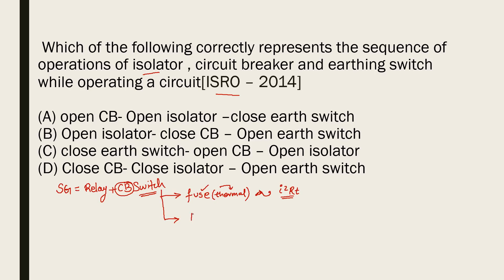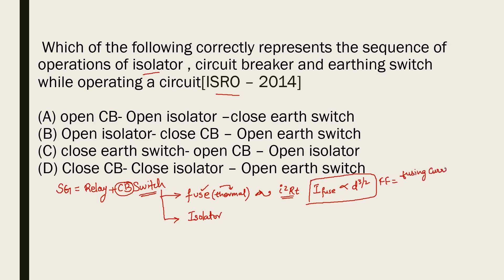Another type of switch is the isolator. The fusing current — the current at which the fuse blows off — is directly proportional to the physical dimension, i.e., diameter to the power of 3/2. There is also a quantity called the fusing factor, where fusing factor = fusing current ÷ fuse rated current. Fusing current is the current at which the fuse melts, while fuse rated current is the maximum current the fuse can carry without melting.